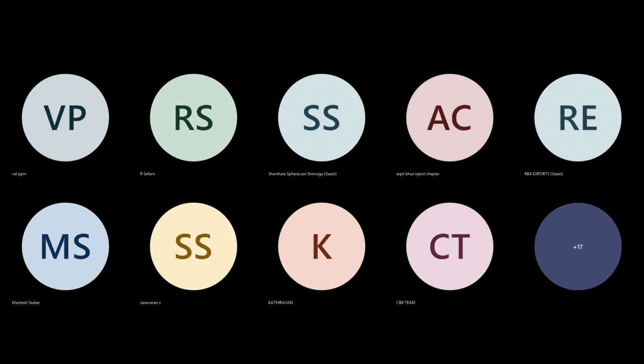For compressor electrical energy conservation, we could try to use a VFD; these are some of the avenues by which you can improve. Then replace pneumatic vacuum pumps with electrical vacuum pumps, air leakage audits can be done, and compressor motors can be replaced with IE3, IE4 rated motors together with a VFD. So we plot the kilowatt hour per ton of metallics, the total compressor energy month-wise, and these are the methodologies I have explained to you.